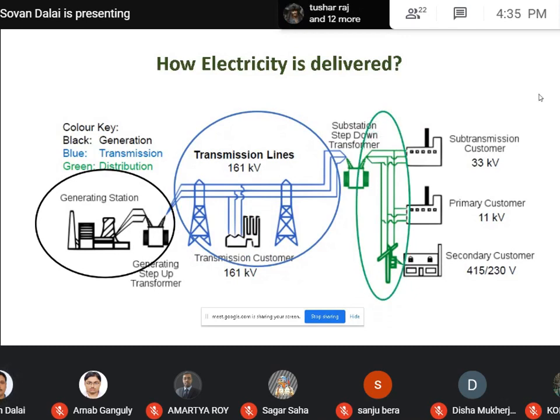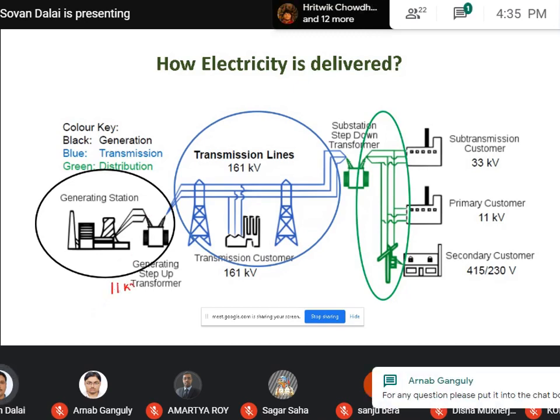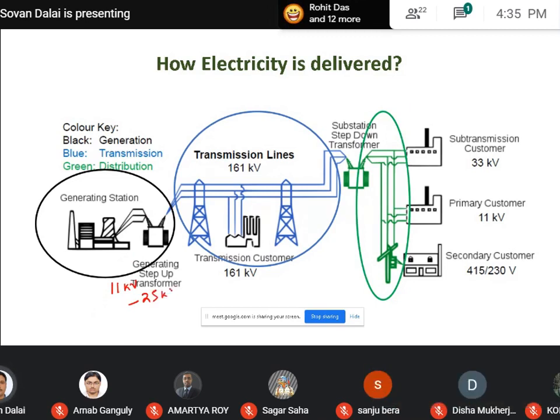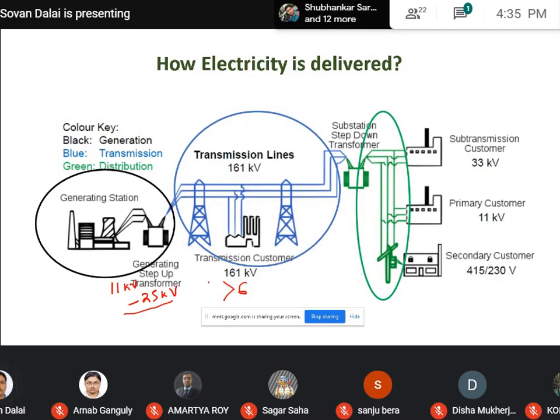Okay, we can categorize these three portions, generation, transmission and distribution, according to voltage level. In a generating station, the voltage is generated by the alternator, in the range of 11 kV to 25 kV. This is an approximate range depending on the alternator manufacturer. Different power stations have different generating voltages, but generally it lies within 11 kV to 25 kV. More than 66 kV is the range of transmission voltage.